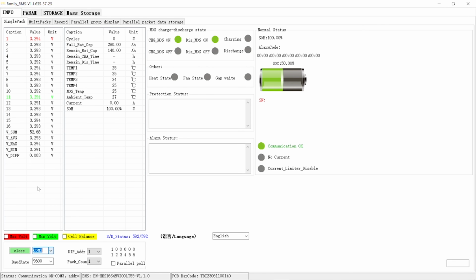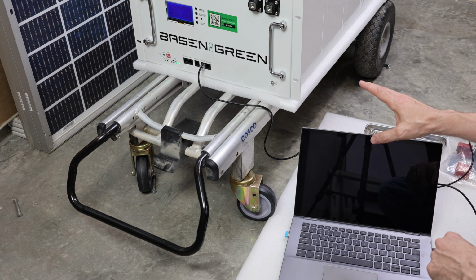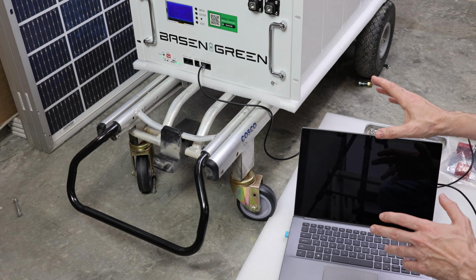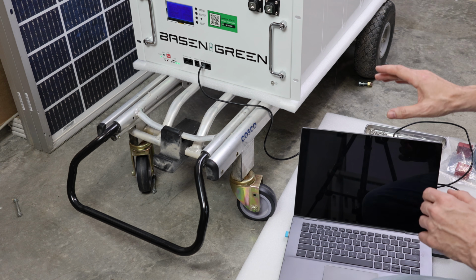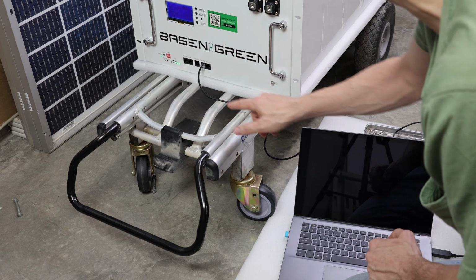The software recognizes the BMS. I can see the voltage of every one of the batteries. Then I just select the appropriate menu, change it to Victron communication protocol, and send that to the BMS. The BMS resets, and now we should be able to connect it to my Victron system through the CAN bus.